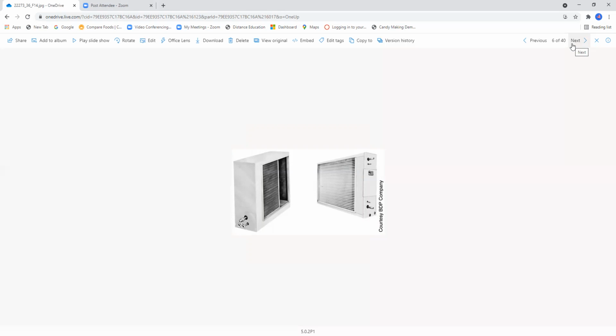I prefer to use what they call the ductboard coils, where you have the coil, which is an inverted A-frame, and you have the ductboard in front of it where you can hook up your ductwork to it. That's very popular in the installation of new homes and replacement work. These horizontal coils, you're not going to see very often, but I will tell you they're out there. And if these things get dirty, you have to take all the ductwork apart to gain access to them. I haven't had any issues other than the fact that they're hard to install. My very first install in my house in Pasadena utilized this type of coil. I will tell you, it took a while to get that in.